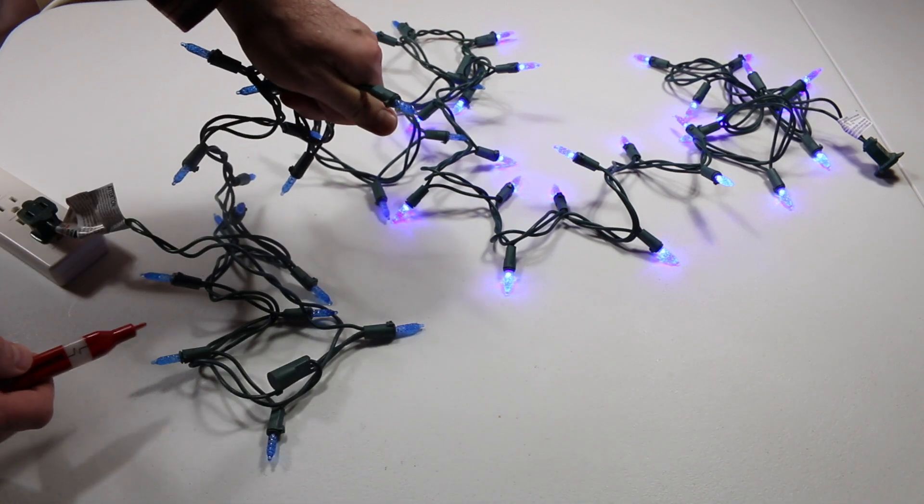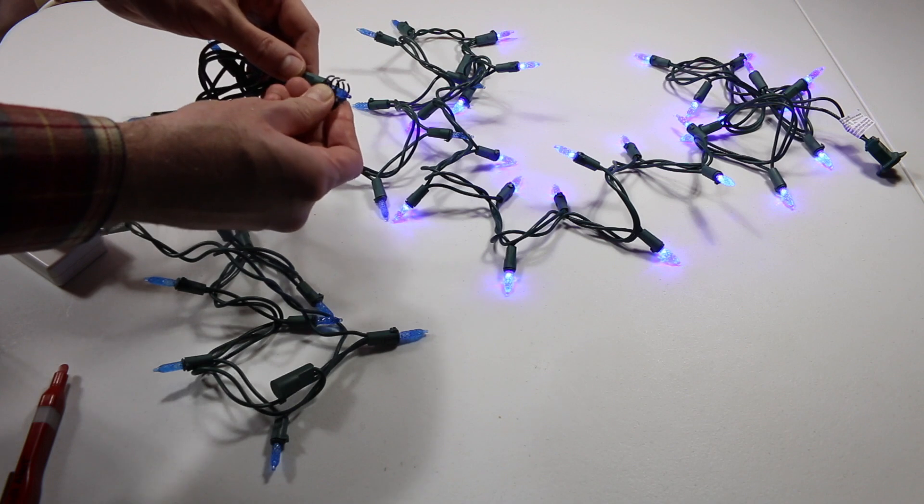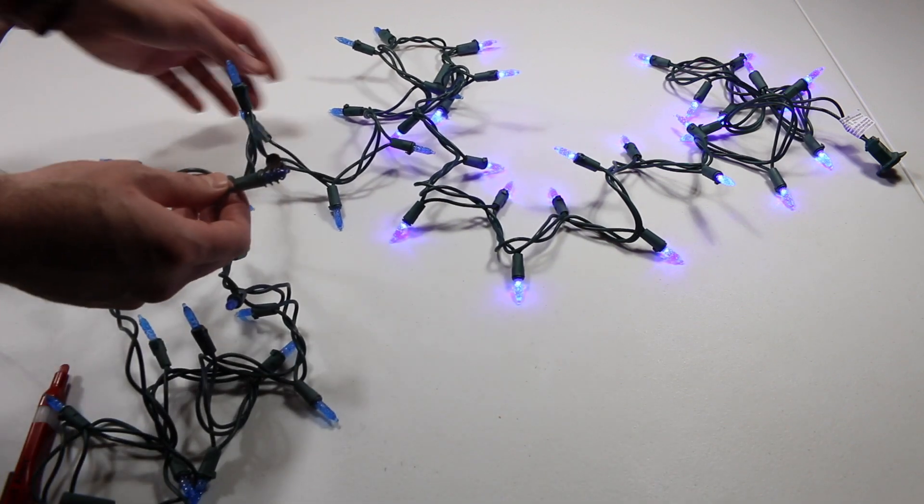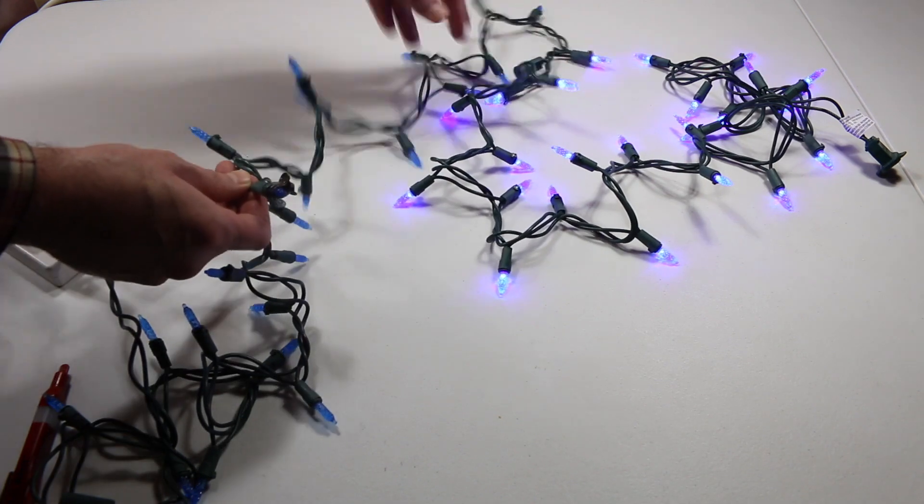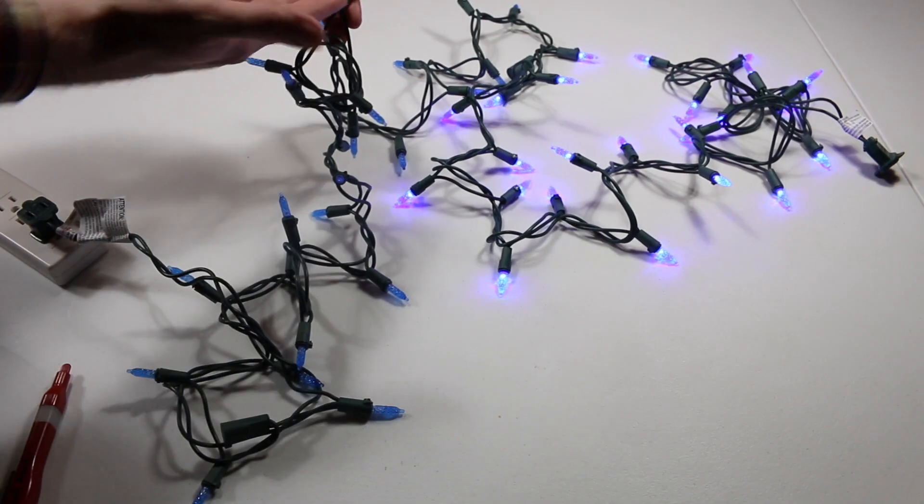I don't have any hot connection there, so I'm going to put a clip on here and I know now the problem is not in this section because I've lost power somewhere from the plug along to here.